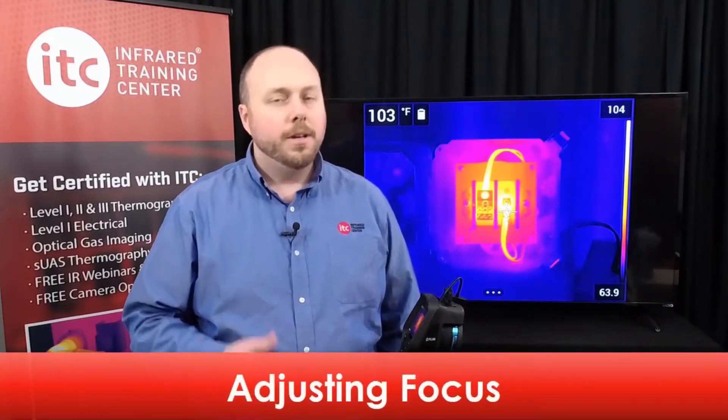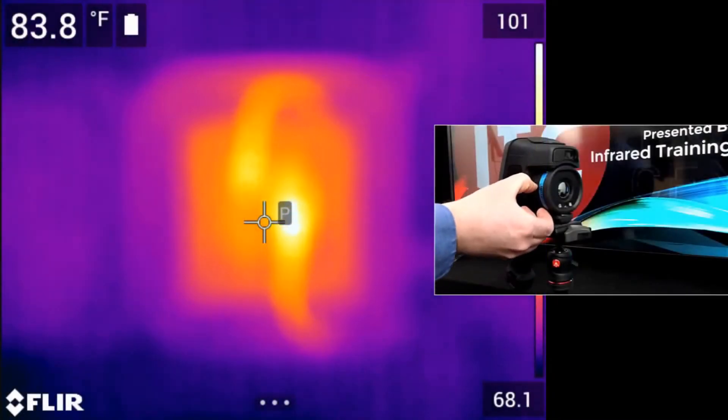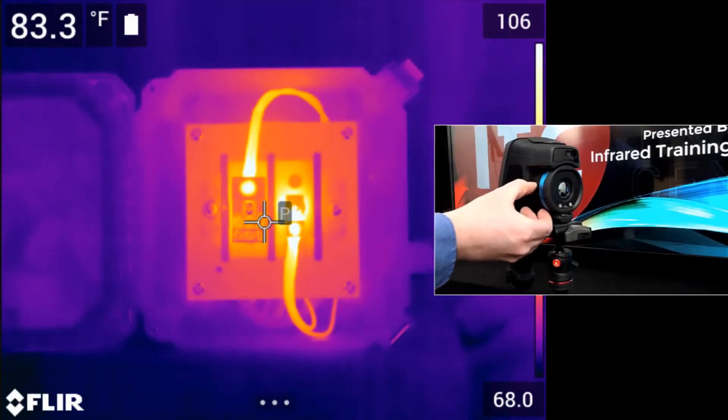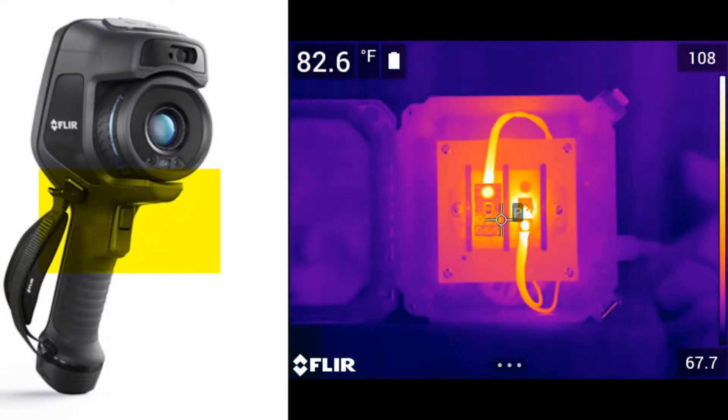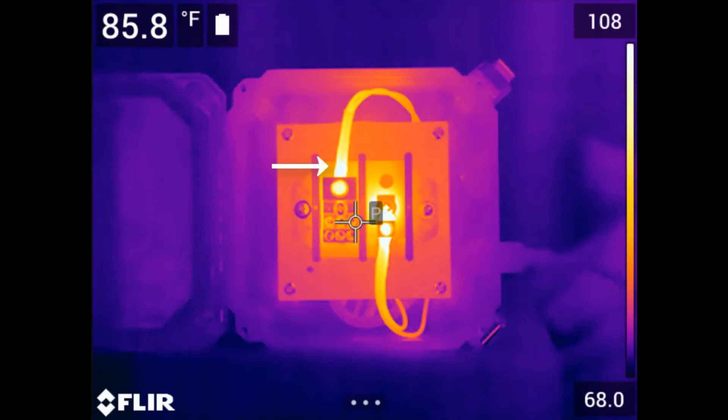As with range, focus is another adjustment that must be made correctly before saving. You cannot change the clarity of the focus once you've captured a thermal image. There are two ways to adjust focus on this series of thermal imager. The first is manual adjustment — turn the lens housing until the proper focus is obtained. The other way is autofocus. Activate it by pressing the top trigger button on the front of the camera. For autofocus to work properly, the target should have good thermal contrast, meaning a distinct difference between warm and cool areas. With targets that are more thermally uniform, it might be better to use manual focus instead.